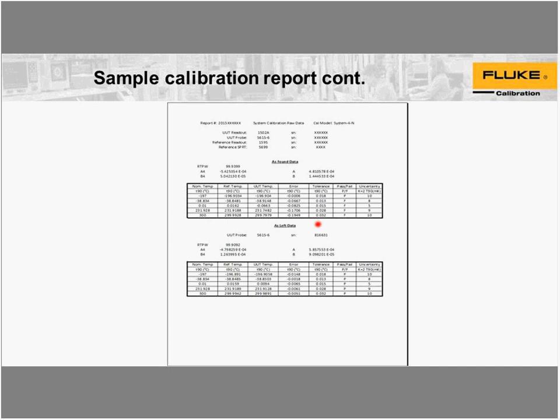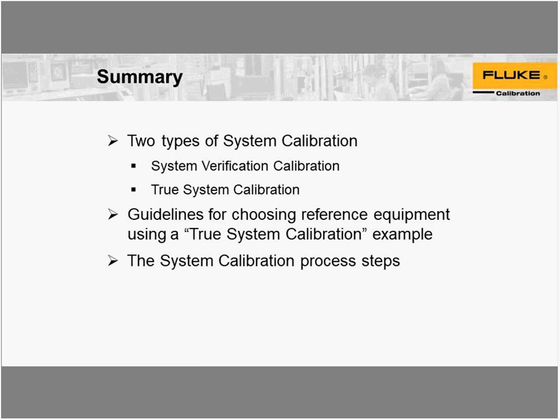So we have good information for the as found data, and it looks like one failed point here on that column. I can't tell if they're all passed except for the one or not. But I know all the ones on the as left data are passed because we verified that earlier. Notice the nominal temperatures on the as found are the same as the nominal temperatures on the as left. And you want to make sure that that's consistent. It adds credibility to your reports. And then our as left data for the reference and for the UUT, our errors, the tolerances, pass fail, the whole thing is all there. So that is a very good product to sell. If you're doing it inside, it also just boosts the integrity of your lab.